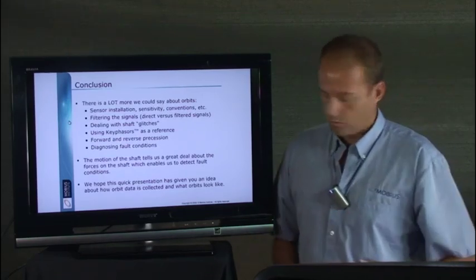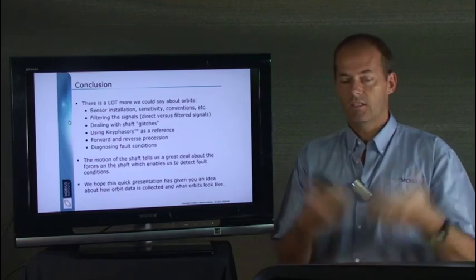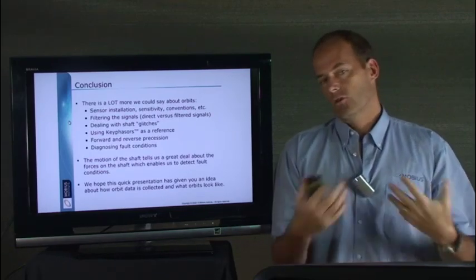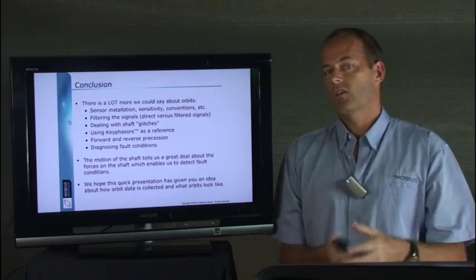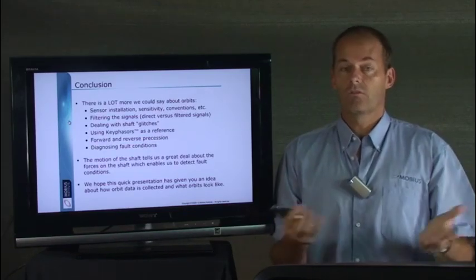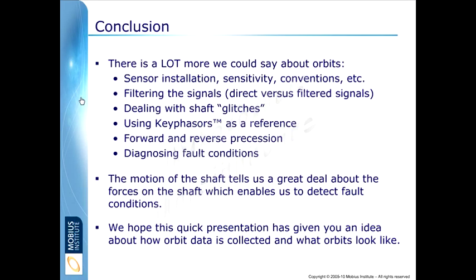So, as I say, there is a lot more we could talk about. We could talk about the sensor installation and the sensitivity and the conventions used. Filtering the signals, whether you're looking at an orbit of just the 1x vibration, the filtered vibration or the direct vibration. Dealing with shaft glitches. The surface of the shaft isn't going to be perfectly flat. It's going to have maybe some surface defects, scratches or whatever. The metal may not be homogenous.